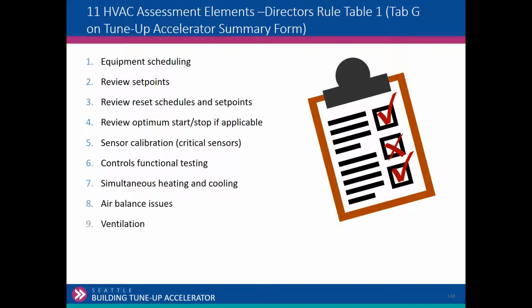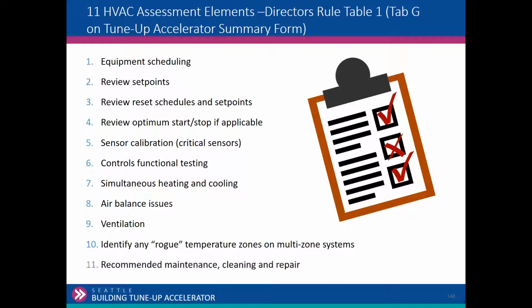Air balance we'll talk about in a little bit, and ventilation. And I mentioned rogue temperature zones. So that's the basic gist if you look at the assessment elements. The final one is maintenance, cleaning, and repair. This is a recommendation. But if you notice that equipment is in ill repair, that it's in need of general maintenance and cleaning, the filters are collapsed into the unit, so the filters need to be changed or whatever, those are recommendations that we want you to make.